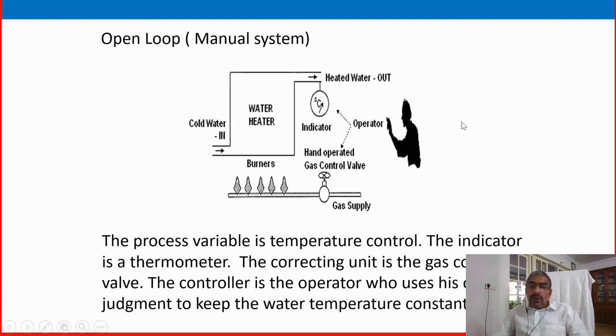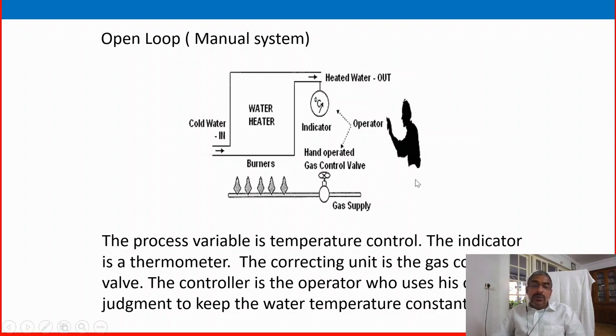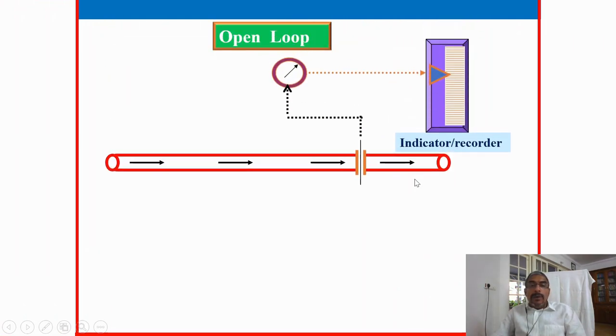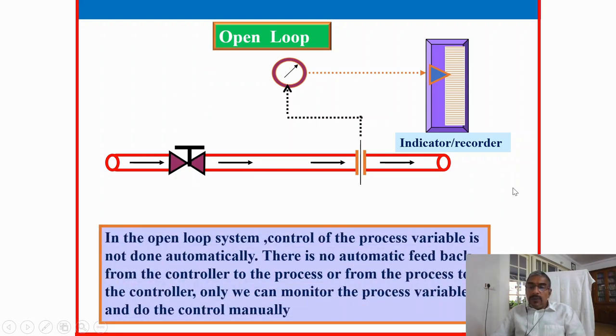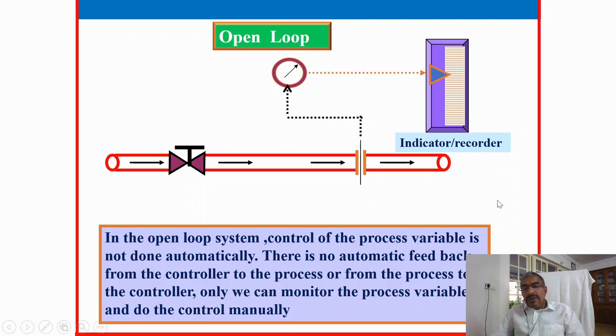An operator standing by and doing adjustments involves a lot of difficulty — this type of open loop system is an older type of control system. Still used for some unimportant applications, but for all important ones it is difficult to control the process properly. In an open loop, the control of the process variable is not done automatically. There is no automatic feedback from the controller to the process or from the process to the controller. We can only monitor the process variable and do the control manually — we can see the value from the indicator and recorder but must manually adjust if above or below set point.